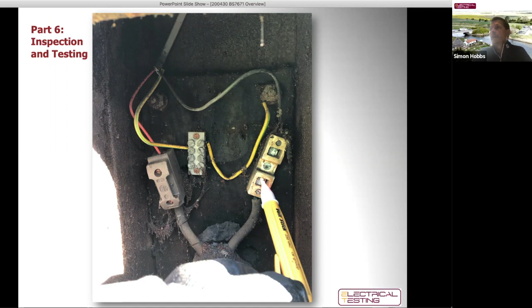Sometimes the equipment itself is quite handy and gives you a natural inspection point. We've got a natural inspection point here and can actually see the cabling inside without having to take covers and doors off, which is really good. These natural inspection points will often extend to cable joints as well, so again we can see inside the cable joint and see the cores and cables there. These are things that have been picked up during an inspection - corroded installations, damaged cables, burnt joints, and so on.